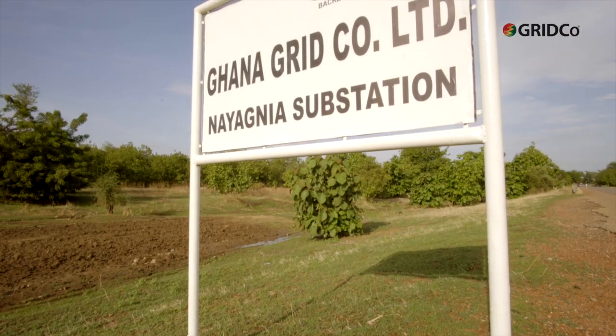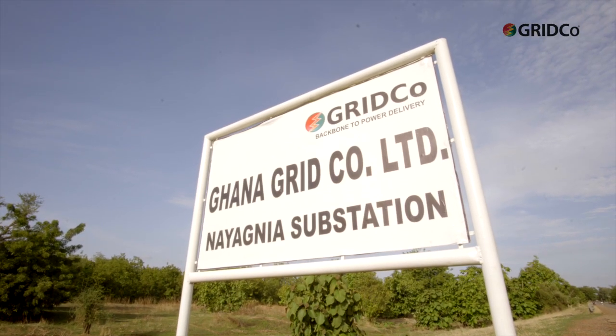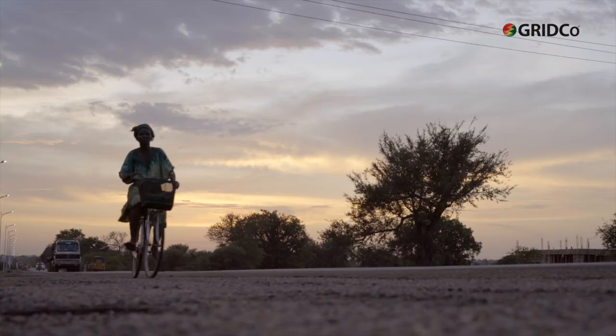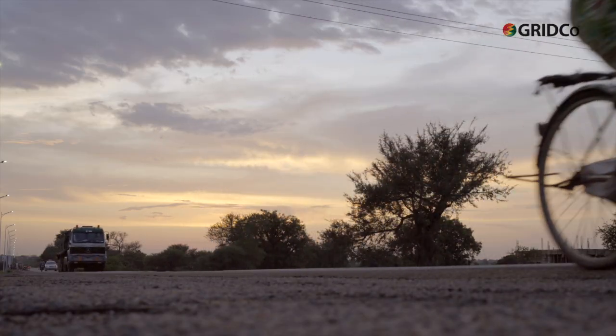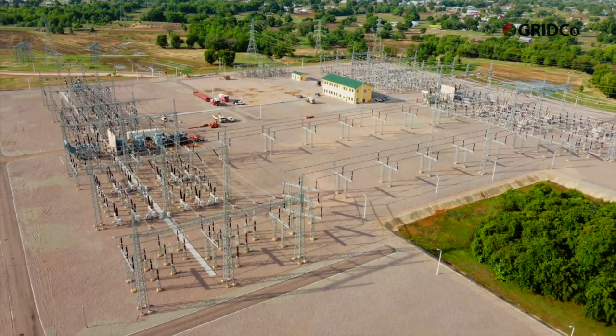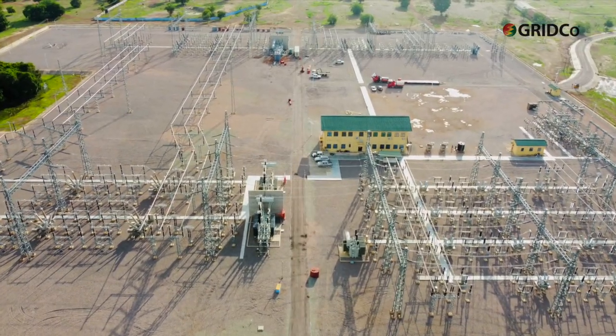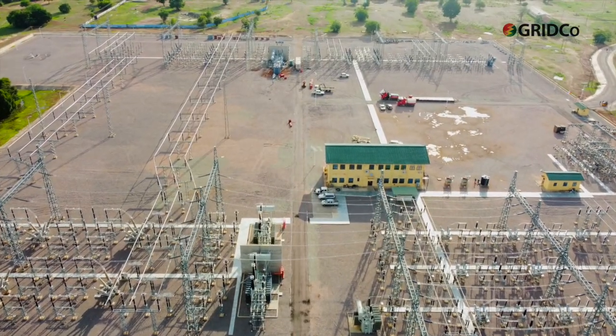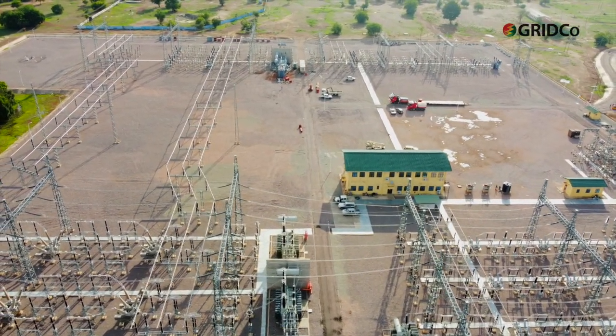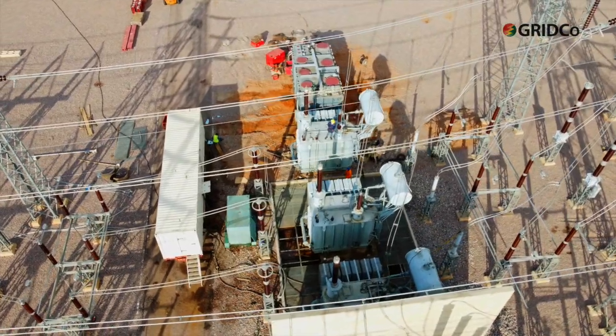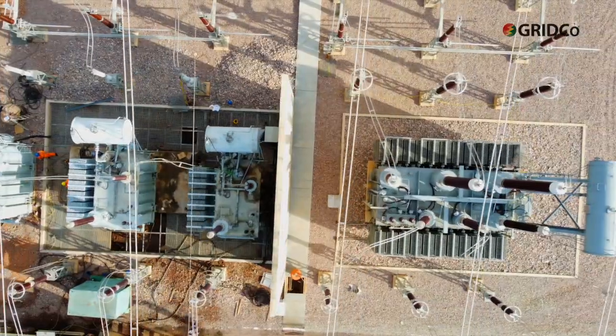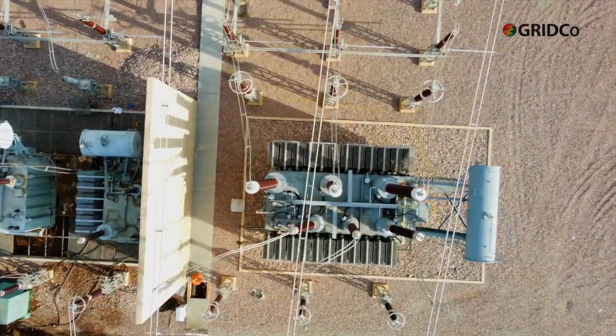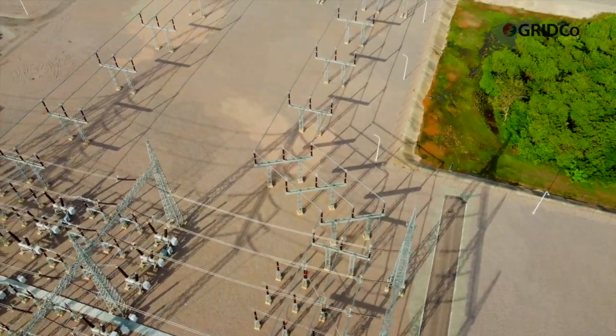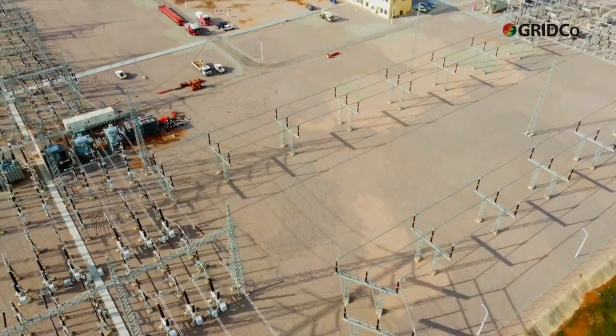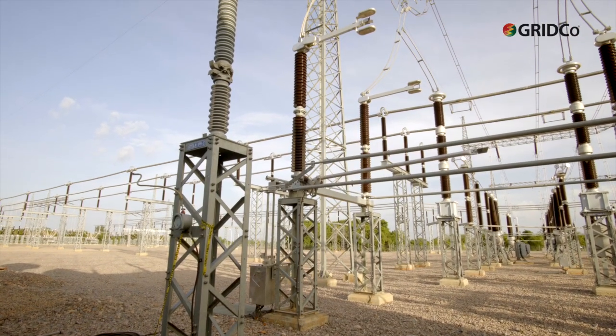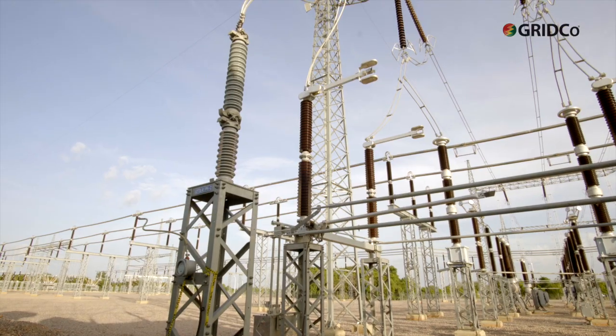Welcome to Nayagnia Substation, NY82, located in Nayagnia, Navrongo District in the Upper East region of Ghana. The station was commissioned in 2018 and comprises two substations of different voltages. One end is 330 kV to 225 kV, solely for the supply of power to Sonabel in Burkina Faso, and the other end is 330 kV to 161 kV, which interconnects into the 161 kV network of GRIDCo.